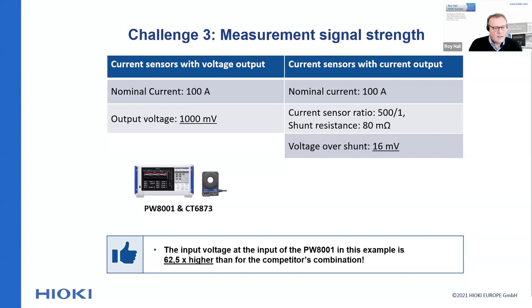Let's take a look at an example. In this example, we measure a current of 100 amp. For this, we need to use an external current sensor. The CT6873 has a range of 200 amps, and it will generate an output voltage of 1 volt when it's measuring 100 amp current at the input.